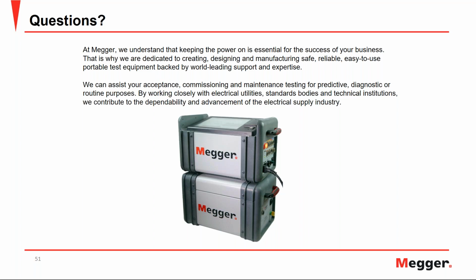So that's basically an industry standardized test voltage. One of the main reasons is for immunity against electrostatic interference. Again, as Dinesh alluded to, we just wrote a paper on this, and there's one section that is dedicated to talking about electrostatic interference. But essentially, your power transformers operate with a high level of electrical noise and interference around them in substations.